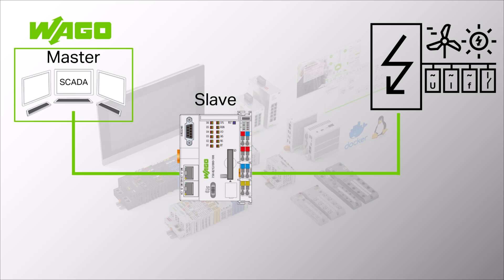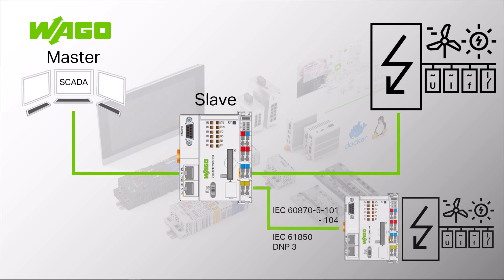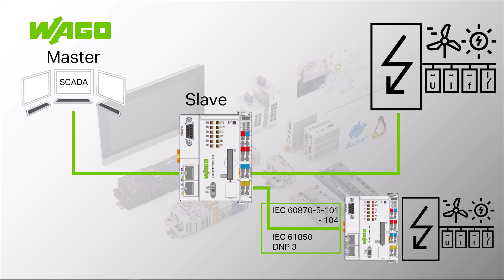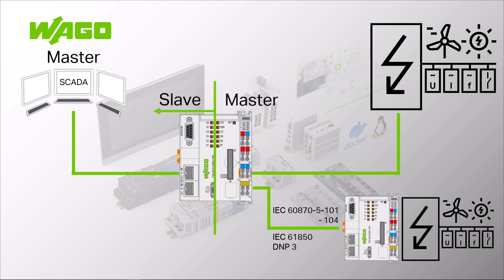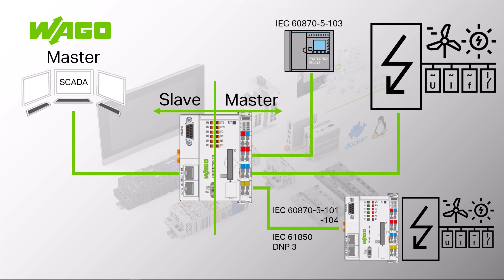A common application for WAGO telecontrol solutions is to connect other system components or devices to a PFC which also communicate via telecontrol. The PFC continues to operate as a slave in the direction of the network operator but then as a master in the direction of the connected peripherals. An important case is the connection of protection devices for which IEC 60870 has its own communication protocol, protocol 103, which we will discuss in more detail later in the video.